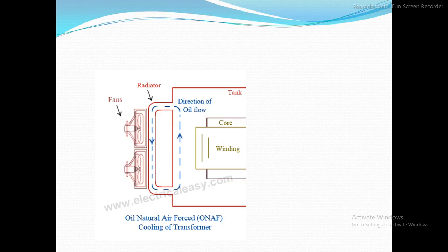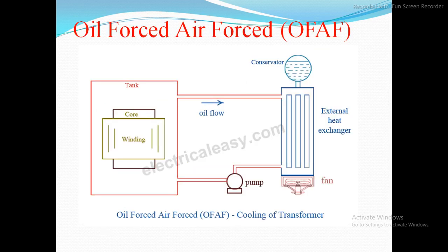of this method. The fans are used, artificial fans are used here. Therefore, it is called oil natural air force. In the next method, we will discuss oil force. When the circulation of the oil is not enough to dissipate the heat, then we have to use oil force by using some additional pump.